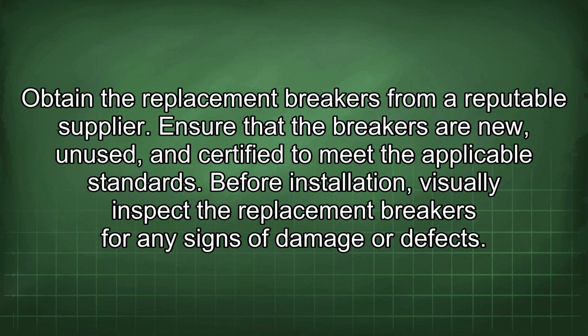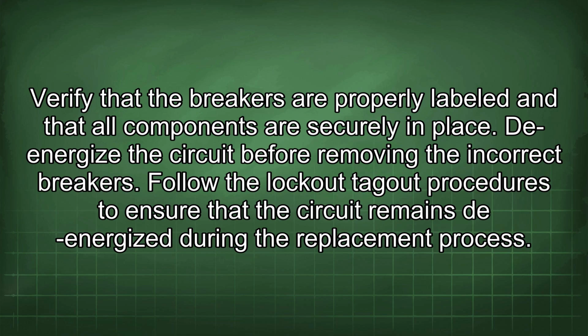Ensure that the breakers are new and not used, and certified to meet the applicable standards. Before installation, visually inspect the replacement breakers for any signs of damage or defects. Verify that the breakers are properly labeled and that all components are securely in place.